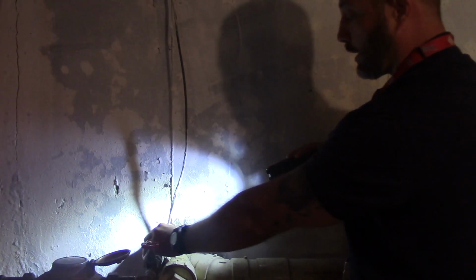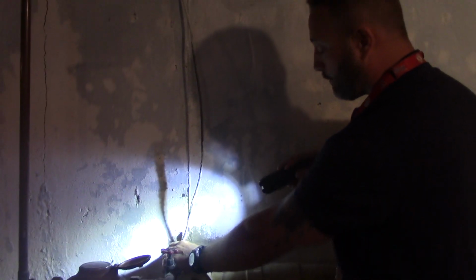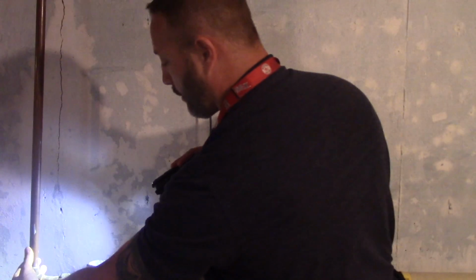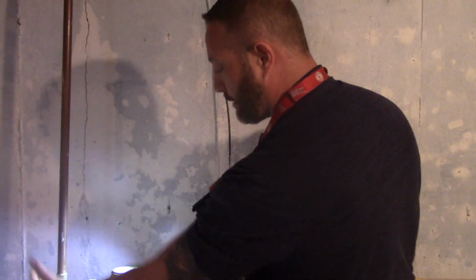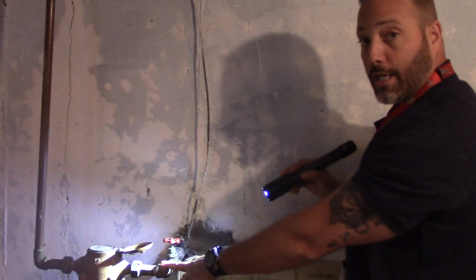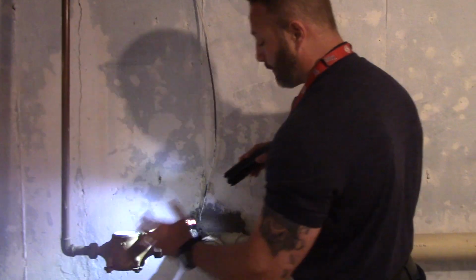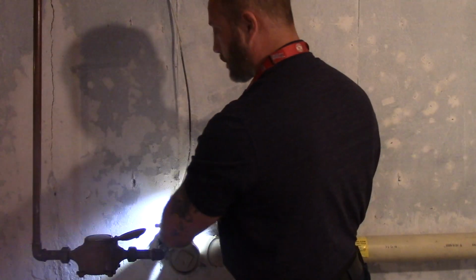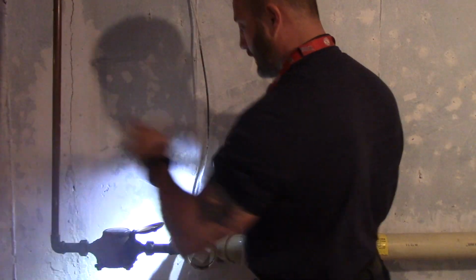What you want is a jumper wire, a ground wire connected to this connection, and then on the other side of this meter. What this meter does is actually act like a light switch. It creates an open circuit. So we want a wire from this location onto this. So this is definitely a defect.